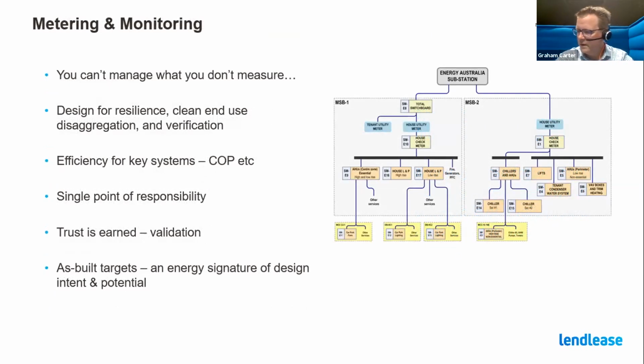So metering and monitoring. I'm going to have to speed up here, sorry. You can't manage what you don't measure. You can have a whole-building target, but it's really important to get it down to an end use level because quite often you have overs and unders. So we need to design these systems to be resilient so they self-check, have child meters that add up, that you can compare to the parent meter so that the system can self-diagnose itself, because guaranteed you will have a problem. And think about how you want to verify performance and design your metering system around that.